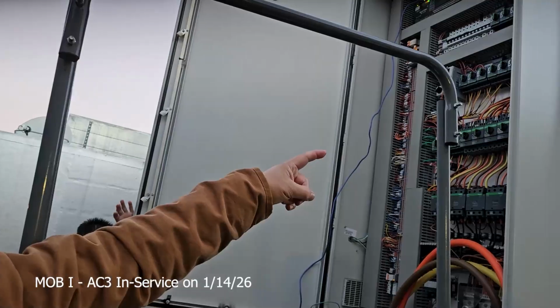So the alarm goes off. Can we reset? We have to reset up here. If your alarm goes, if they try 3 times and they lock out, that's a manual reset. Then you'd have to shut off. Once you find out it's a compressor alarm, you'd have to shut the MSP, which would be for your compressors, will be down here. Those 4 large ones.